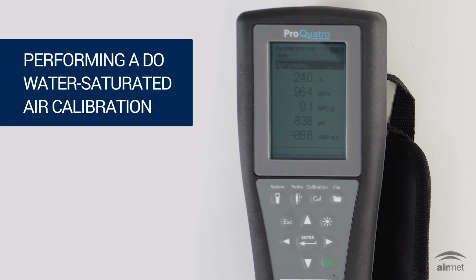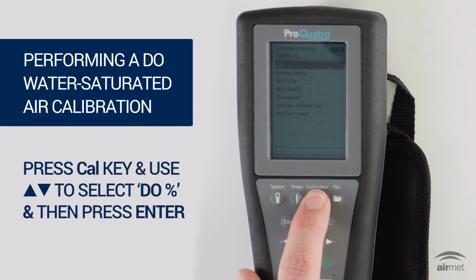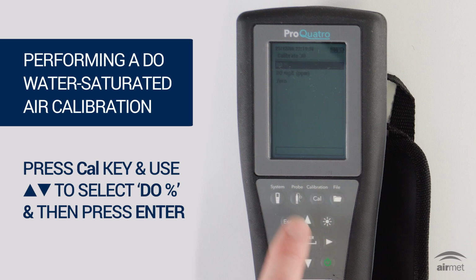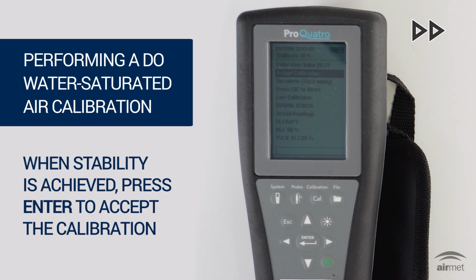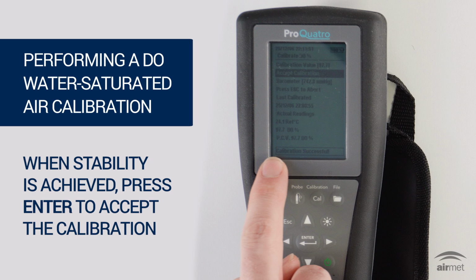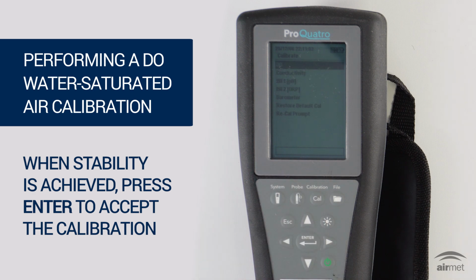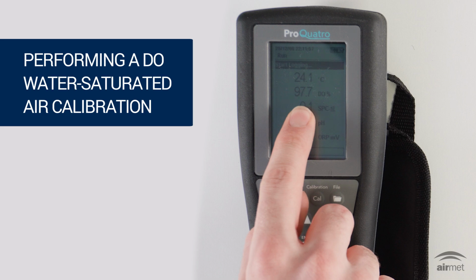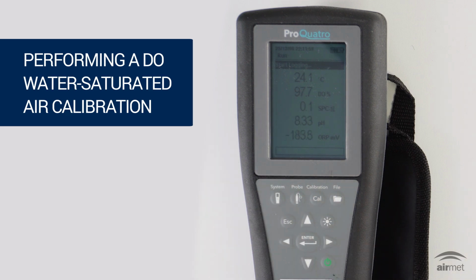To perform the calibration, press Cal, highlight DO, then press Enter for DO 100. Wait for stability and then highlight Accept Calibration. A confirmation message, Calibration Successful, will appear, and the instrument will return to the calibration menu. This also applies to the single-point DO percentage calibration.